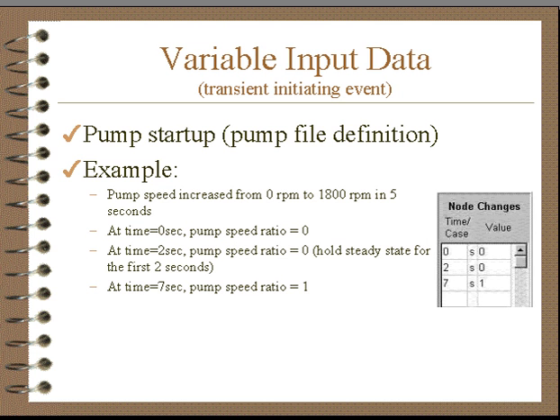If you are starting up a pump described by a file, you have to designate the speed. There's no way to calculate the startup speed. Here we're starting up this pump, holding the steady state condition where the pump is off for the first two seconds, and then starting it up in five seconds.